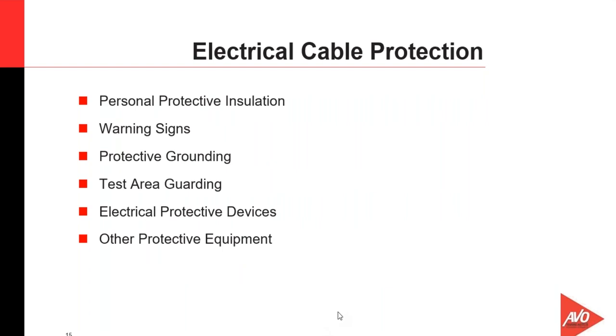So we've reviewed the hazards. We've got shock, arc, and blast type hazards that we're dealing with. In cable testing and cable fault locating, we're connecting to and working in systems that were previously energized. So it's very important that we take the right precautions and apply the right PPE. We're going to talk about personal protective insulation, warning signs, posting warning signs and looking at warning signs on equipment, protective grounding to be used in the test areas, test area guarding.